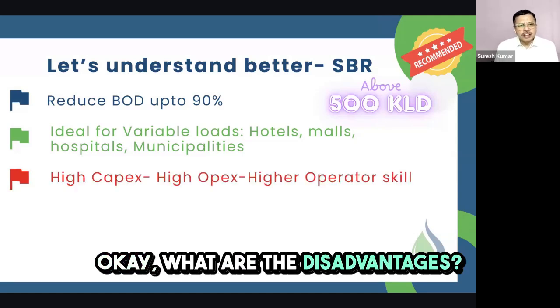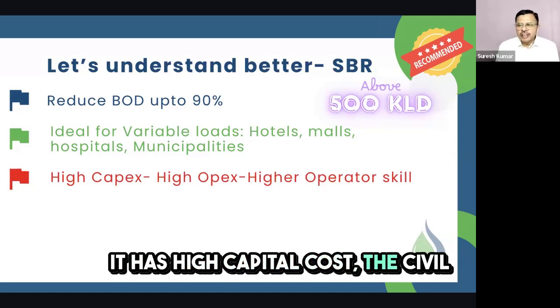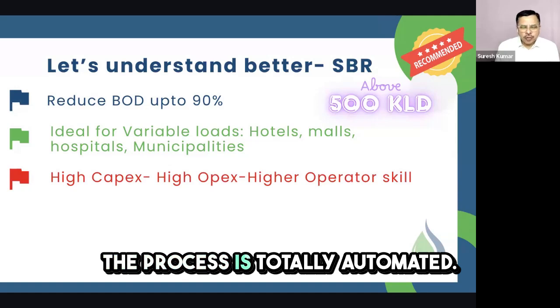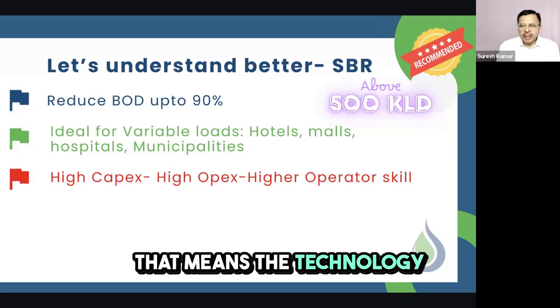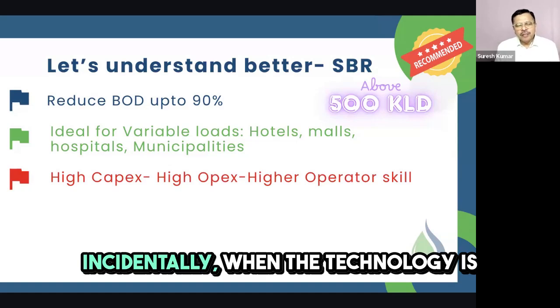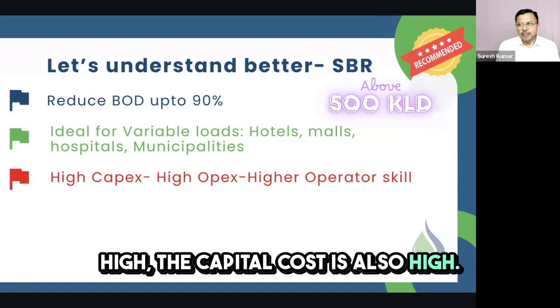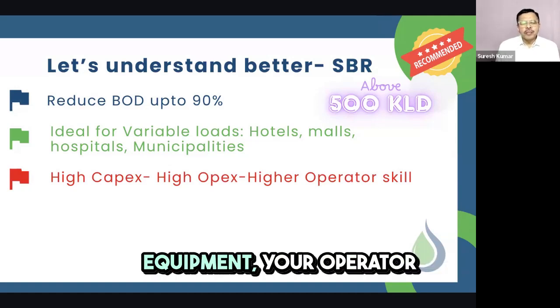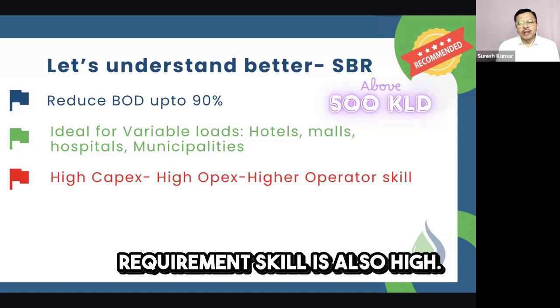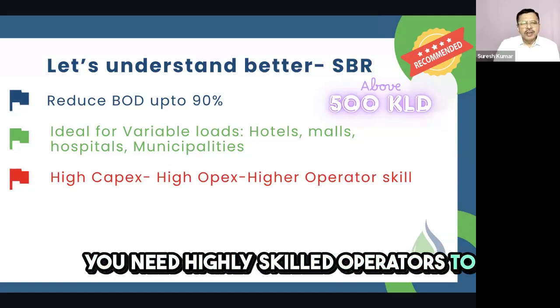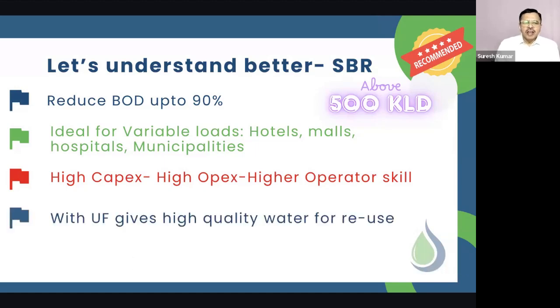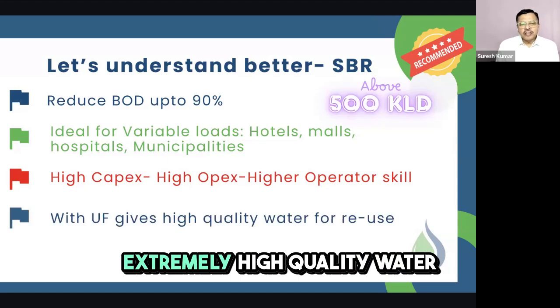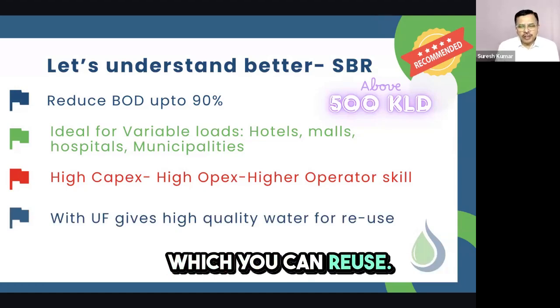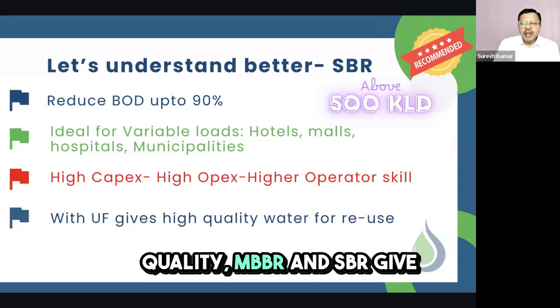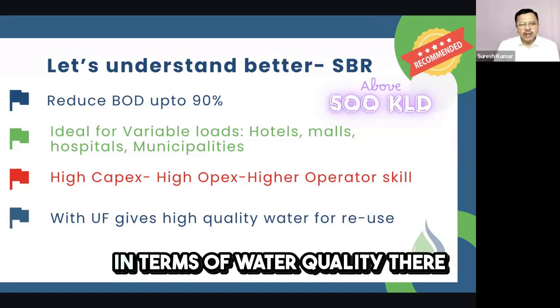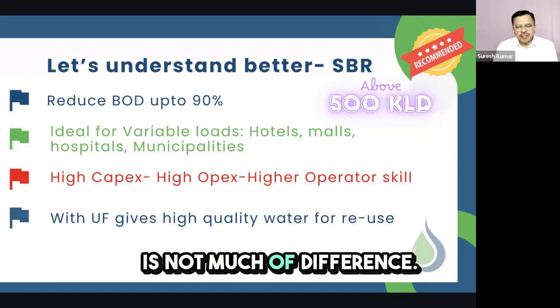What are the disadvantages? SBR has high capital cost, and civil construction cost is high. The process is totally automated, meaning the technology level is high, and with high technology comes high capital cost. Running this equipment also requires highly skilled operators to keep the plant functional. Along with UF, SBR gives extremely high quality reusable water. However, MBBR and SBR give fairly similar water quality — there isn't much difference there.